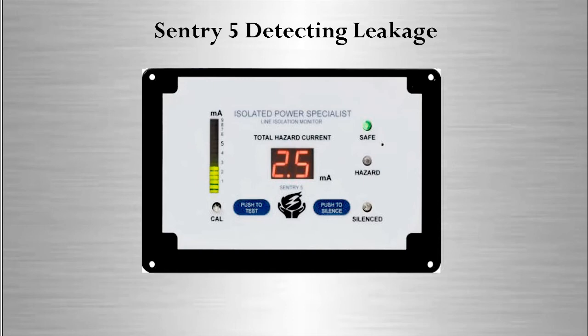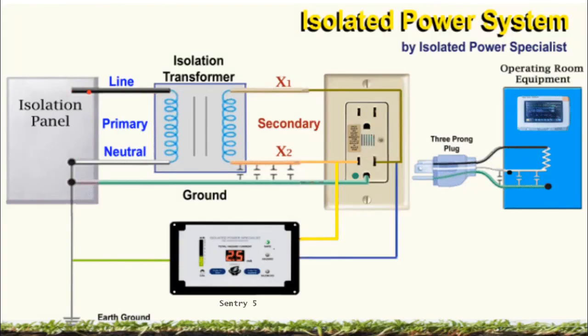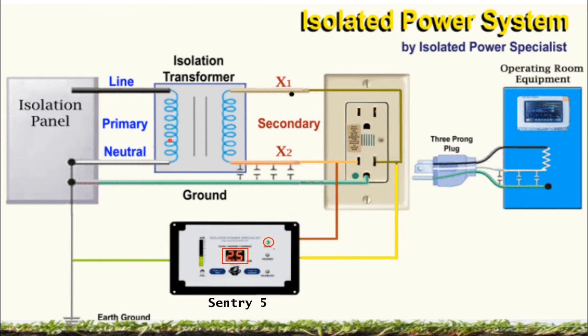Now that we've looked at the isolated power system and the line isolation monitor, let's merge them. As you can see, the Sentry 5 line isolation monitor is monitoring both X1 and X2 to ground. And currently, we have no alarmable leakage, as indicated by the green safe light, also by our digital readout of 2.5 mA, and displayed in our colored bar graph.